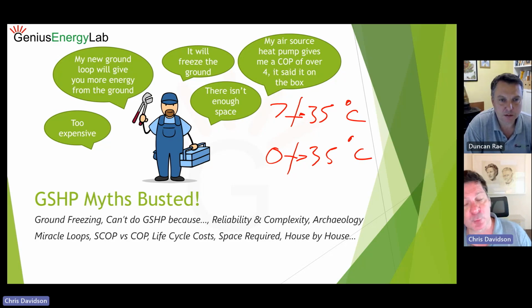We contributed to some work by Element Energy fairly recently, and we concluded that in the UK, real world UK, you should be looking at 2 to 2.2 for an air source seasonal COP and 3.5 to 4 for a ground source COP if it's designed and installed properly.